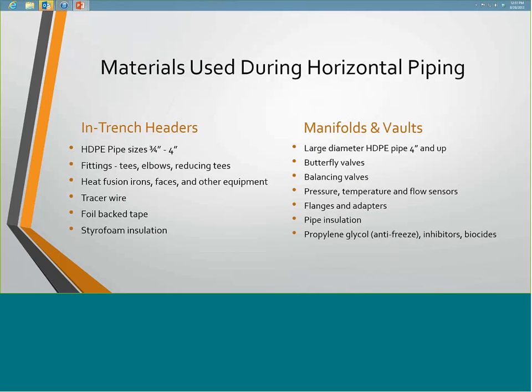When you get through with the loop installation, you go into the trench headers, and you end up using a wide range of high-density polyethylene pipes, typically between 3/4 to 4 inch, leading up to the manifolds. There are a lot of fittings - tees, elbows, reducing tees. Everywhere a loop needs to be connected to that horizontal pipeline, there's a fitting, so we go through boxes and boxes of fittings on every job.